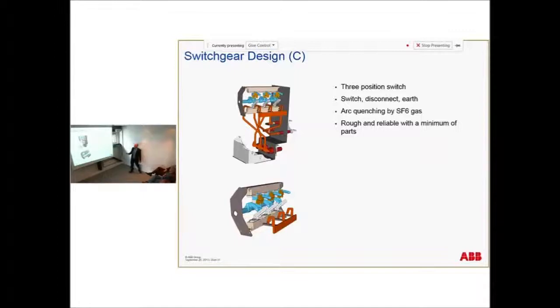Inside it will look like this, where you have the 3-position switch: on, off, earthed. And you see the bushing, the copper, and it's round copper, very geometrical, nice shape, in order to minimize the width and depth of the switchgear up to the breaker itself. So the breaking is in SF6 gas. SF6 in this case has two purposes: insulating medium and breaking medium.